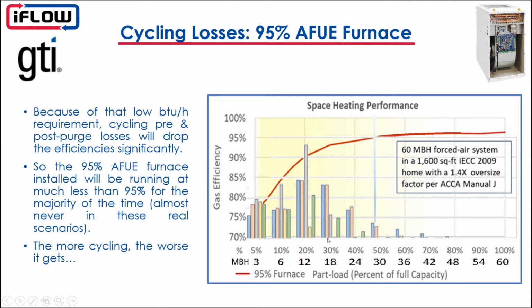But in the city, where a lot of the driving of that furnace will be, if you will, the efficiencies unfortunately are not where they need to be, and that's because the unit is cycling. As we saw with our two-stage furnace, even at the 60,000 BTU level, the minimum input was 42,000, so up at this 70% range. Any of this distribution is going to be below that 70, so the furnace is going to come on and deliver 42,000 BTUs into the space, but that is more than the heat we need, so the room is going to heat up quickly, the thermostat is going to see that and shut down, and it's going to cycle. And every time we cycle, all the heat that we've built up in the heat exchanger has to be post-purged out.